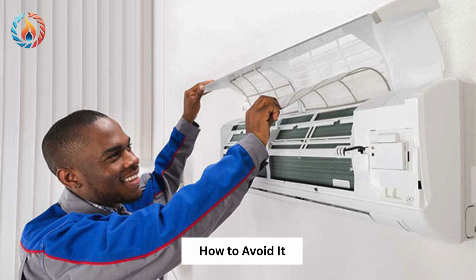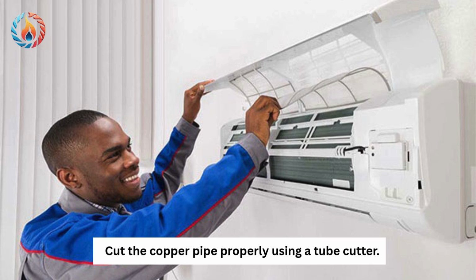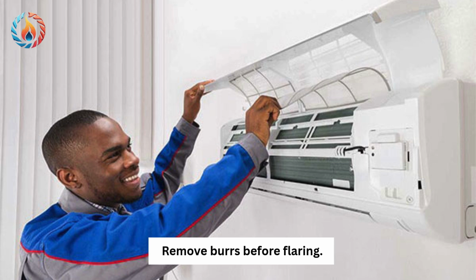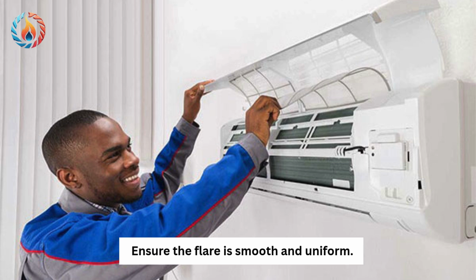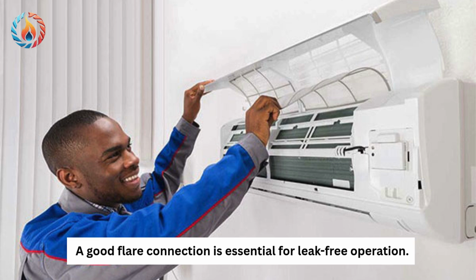How to avoid it? Use a quality flaring tool. Cut the copper pipe properly using a tube cutter. Remove burrs before flaring. Inspect the flare surface carefully. Ensure the flare is smooth and uniform. A good flare connection is essential for leak-free operation.